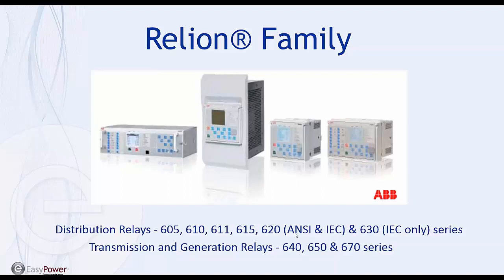EasyPower has modeled all the standard overcurrent curves in there, and now we have the arc flash protection modeled. And we can also use the built-in arc flash feature that's already in the relay, which from what we've seen before is offering, for all practical purposes, the same amount of arc flash protection using the lens sensors.